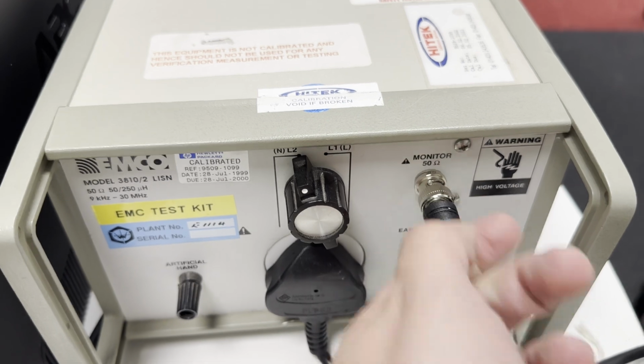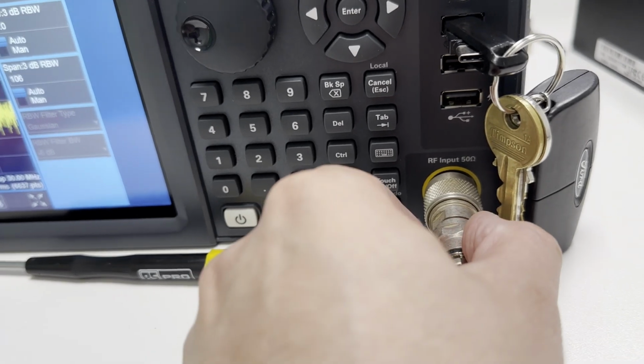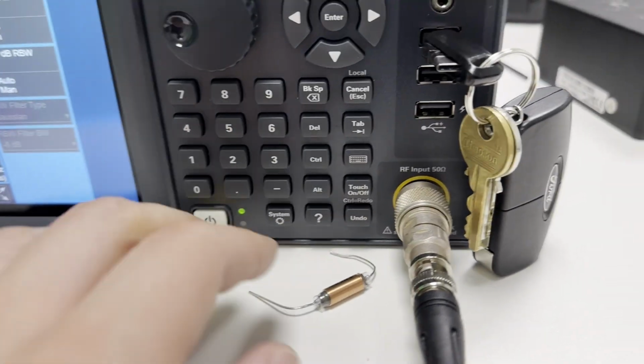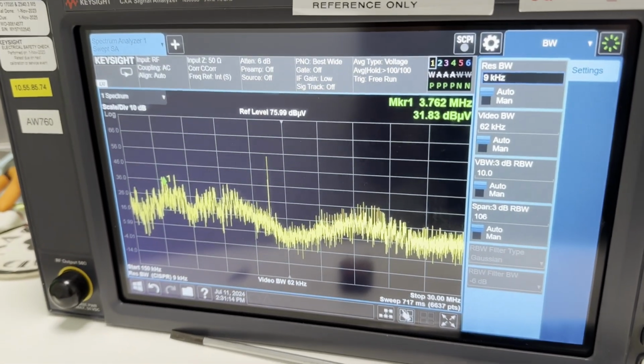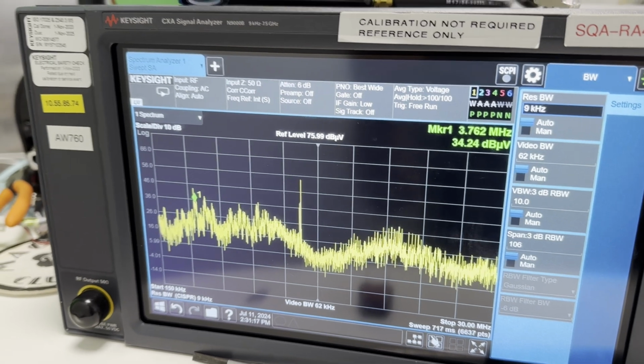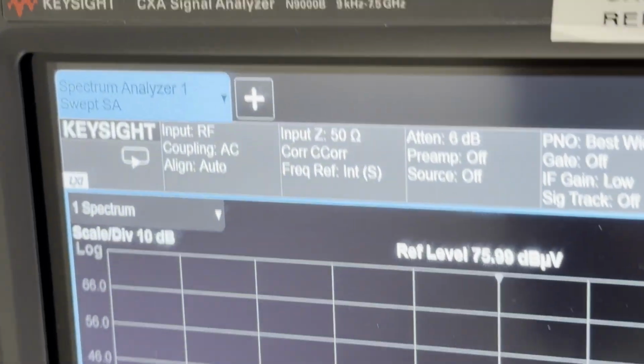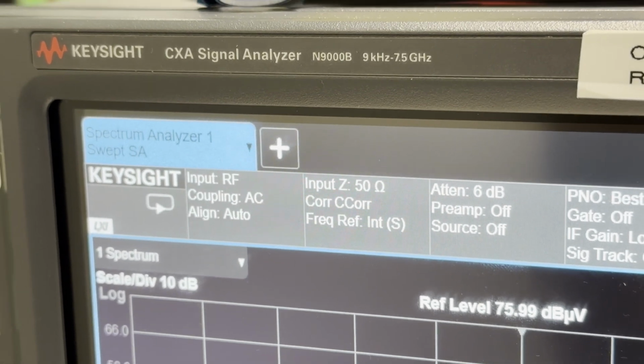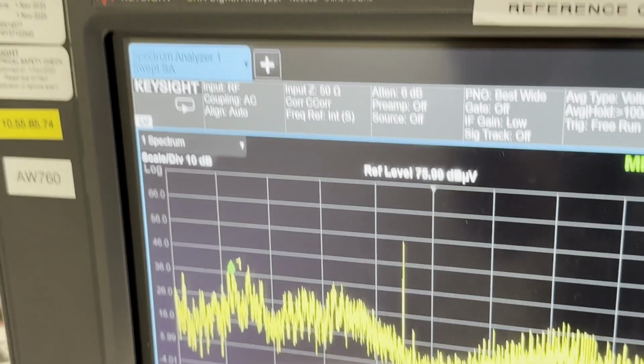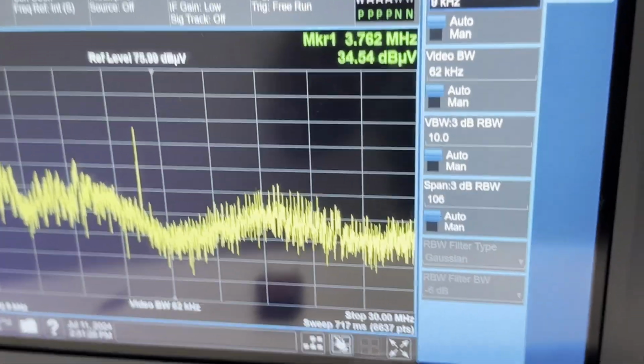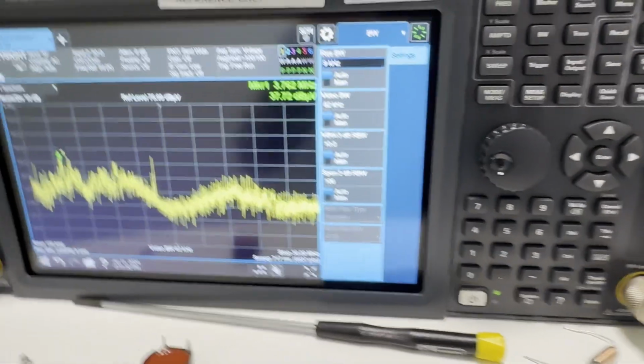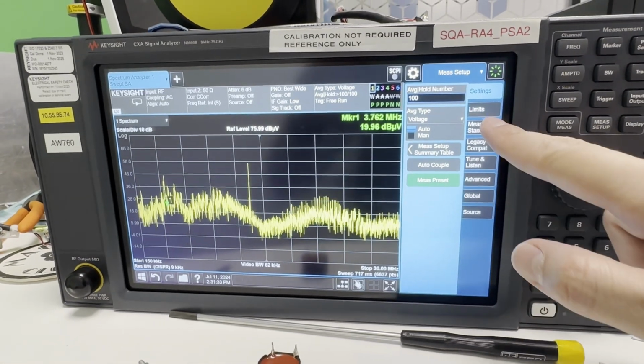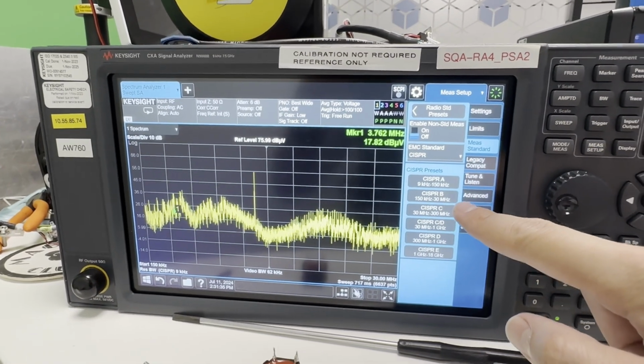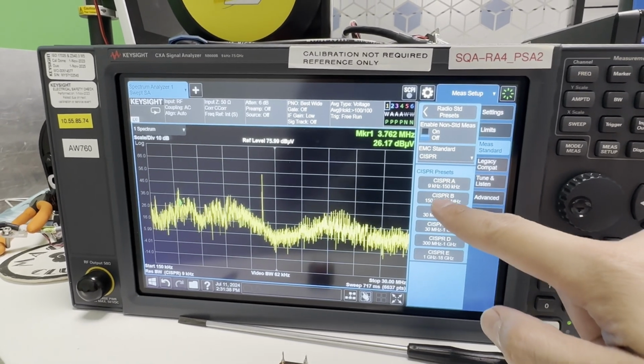So the data is captured through the monitoring BNC cable, and then that's plugged into the RF input of the Spectrum Analyser. And here is the Spectrum Analyser itself, in this case the Keysight N9000B, so it's a rented Spectrum Analyzer. What's good about this box is that it allows you to set up a preset for different measurement standards, such as this one.